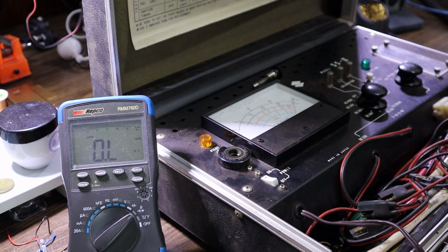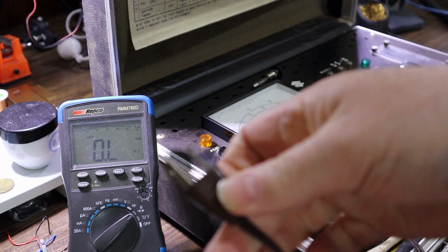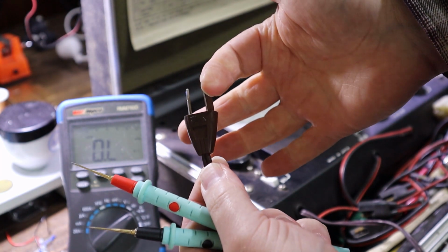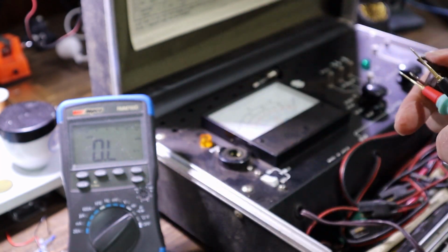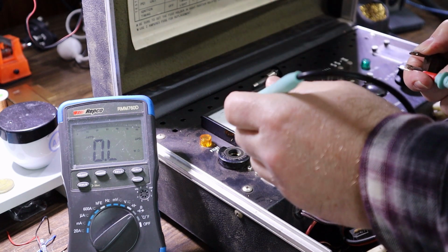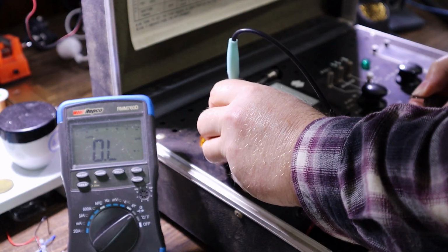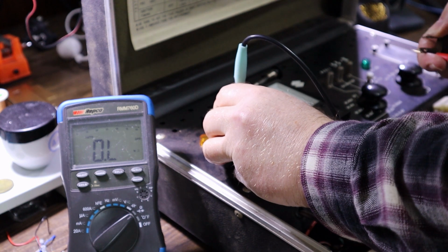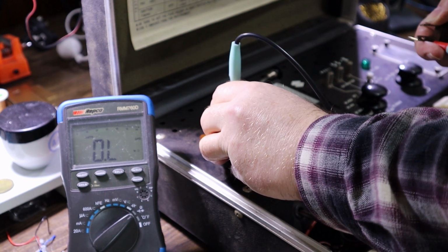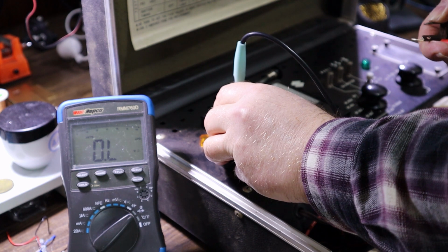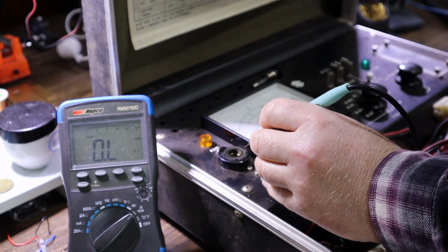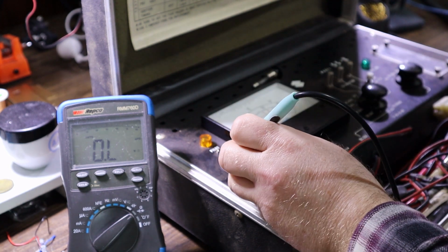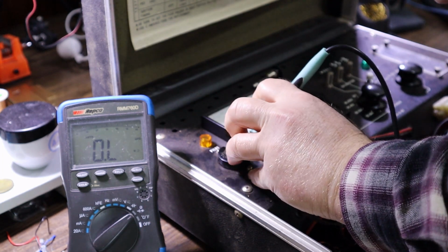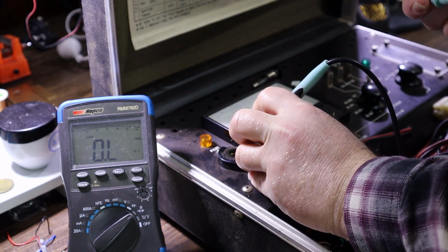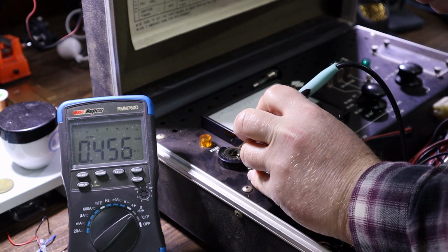So what if we go from neutral? In this country, neutral is on the right, so we've got phase and neutral. If we go neutral to, what about down in the bottom of the fuse socket? I don't know which one's in and which one's out. Got nothing happening there. What if we go to the metal, the thread? We got anything there? No. Or there.